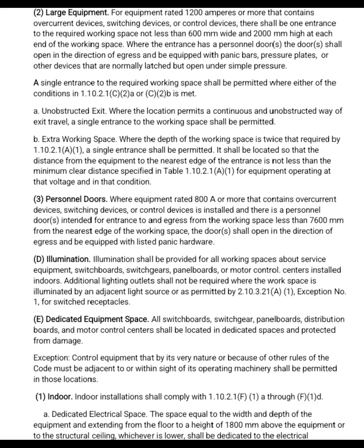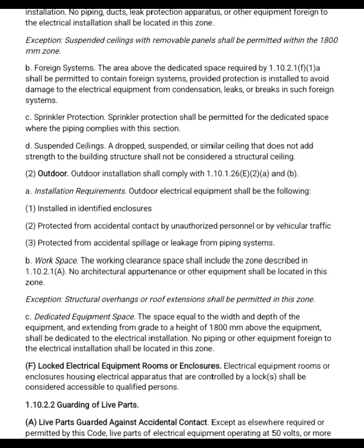In illumination, workspaces around electrical equipment must be well lit. Extra lights are not needed if there is already enough nearby lighting. And indoor installation must follow rules. The space must be kept clear to protect the equipment and allow safe work. B. Foreign systems. The area above the dedicated space required by 1.10.2.1 F1 A shall be permitted to contain foreign systems provided protection is installed to avoid damage to the electrical equipment from condensation, leaks, or breaks in such foreign system.